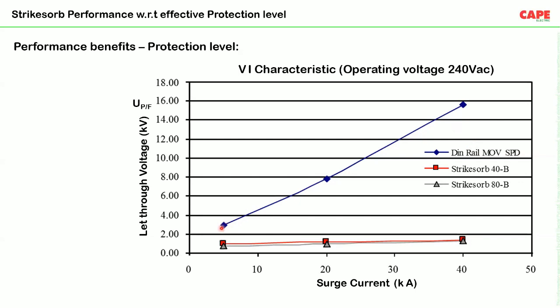Say, for example, in a DIN rail mounted SPD with a connecting wire of, let's say, 250 millimeter, here you can see the surge current on the x-axis and the let-through voltage. Depending upon the surge current, the effective voltage that goes into your equipment is higher and higher. Say, for example, for a surge of 30 kiloampere, up to 12 kV goes into your equipment. That means your equipment is ultimately not protected. It is because of the wire length, because a DIN rail SPD needs a bit of wire and an HRC fuse to connect. Whereas in comparison, the bus bar mounted SPD is connected directly on the bus bar. As a result, the protection level is much lower. You get very good protection.